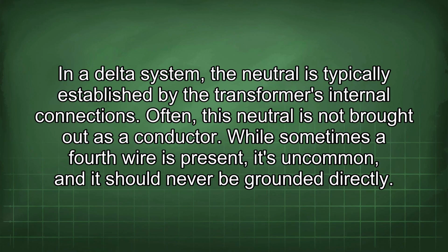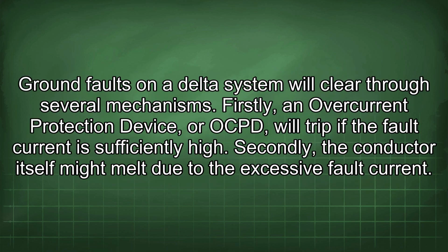In a delta system, the neutral is typically established by the transformer's internal connections. Often, this neutral is not brought out as a conductor. While sometimes a fourth wire is present, it's uncommon, and it should never be grounded directly. Ground faults on a delta system will clear through several mechanisms.